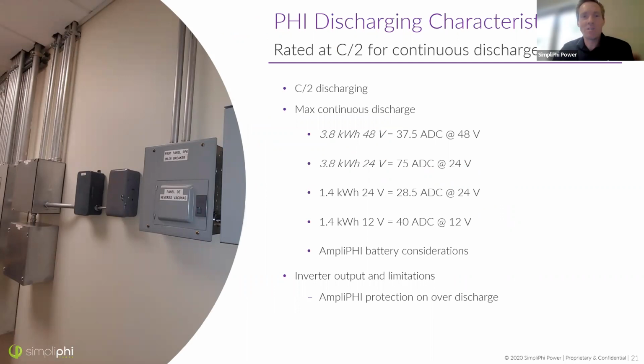Okay, going back to talking about Phi batteries and discharging characteristics. Batteries are rated for a C/2 continuous discharge. For our 48 volt and 24 volt Phi batteries, that is 37.5 amps for the 48 volt version. The 24 volt version is 75 amps. That's per battery, so if you double the number of batteries, you double this rating. If I have 4 of the 3.8 kilowatt hour 48 volt Phi batteries, I'd have an ability to discharge at 150 amps continuous. The other way to think of that is 1.9 kilowatts per battery.